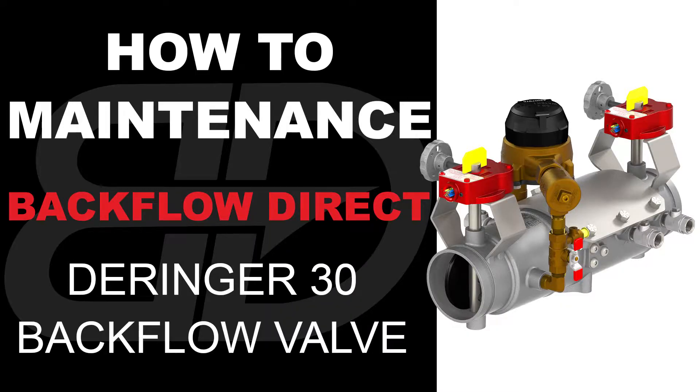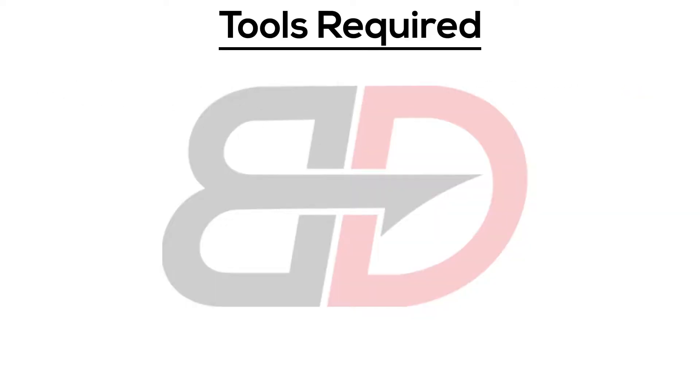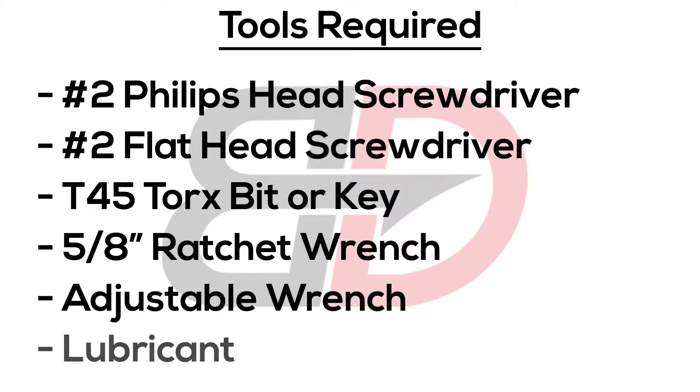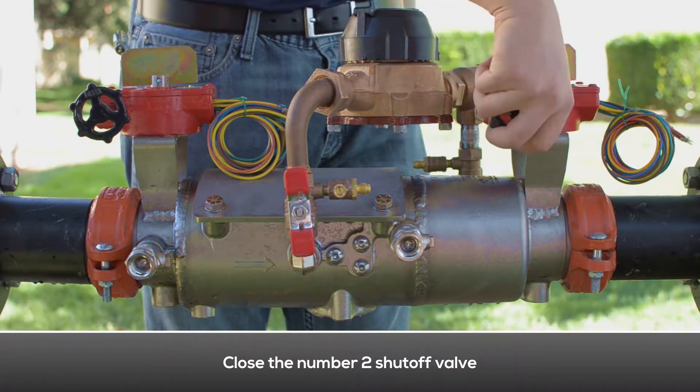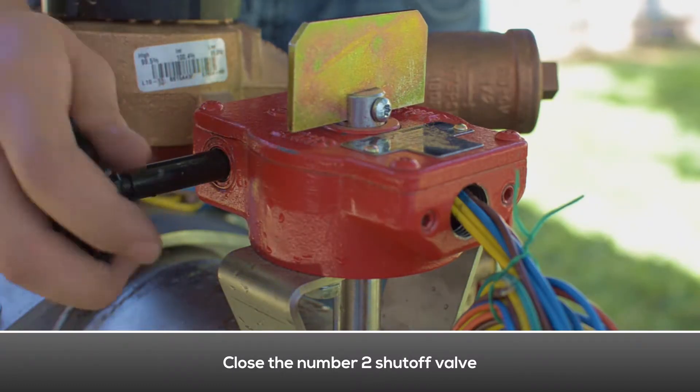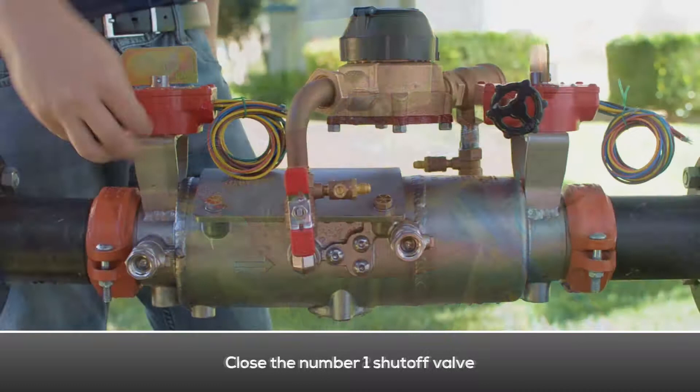The following video contains step-by-step instructions on how to maintain the two-and-a-half through four inch Deringer 30 double check detector assembly backflow preventer. These are the tools required. Close the number two shutoff valve, then close the number one shutoff valve.